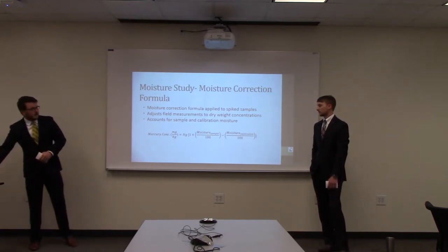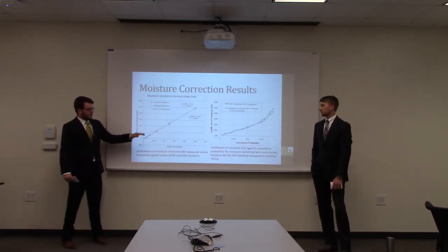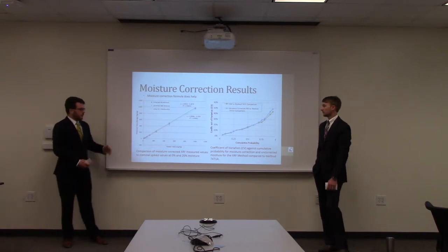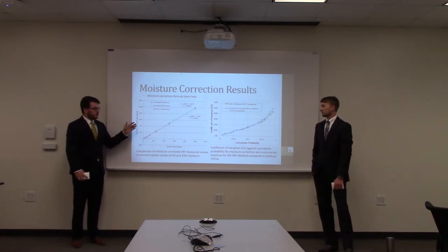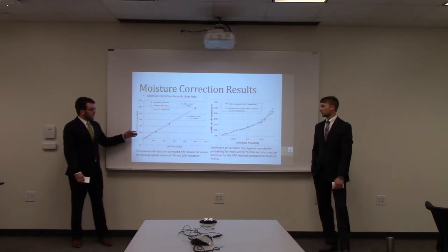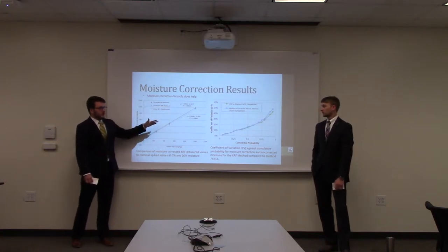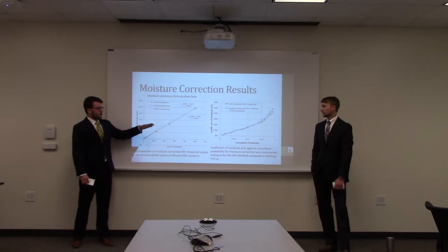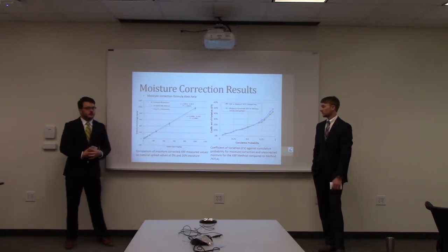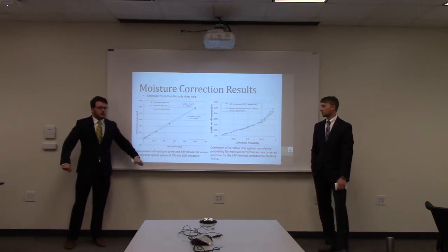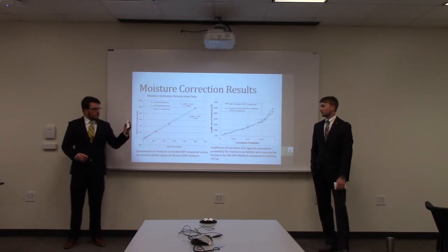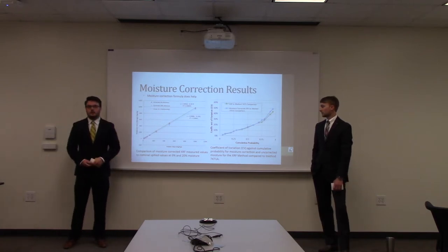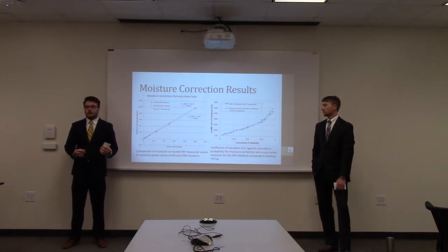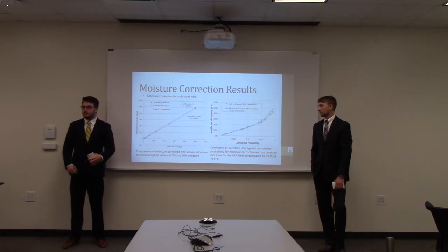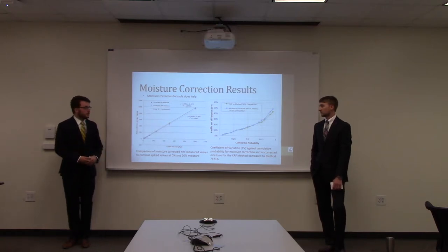After we applied that, we actually had a lot better results, as you can see in this graph. Once we applied that to the same data, our 0% moisture tightened up a whole lot, and our 20% moisture tightened up too, but not quite as much. We were able to take the samples, apply this correction, and figure out that overall, moisture is not going to play a huge effect in whether we're coming up with an accurate result when using this instrument in the field.